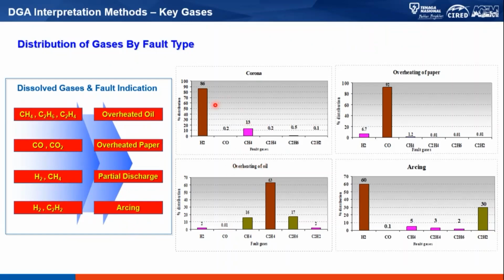Based on the distribution of these gases, you can see here on these bar charts on the right - the composition in terms of distribution, for example for corona or partial discharge, hydrogen is the major gas produced at perhaps lower temperature. When you talk about overheating of paper, more CO or carbon monoxide is produced compared to other gases. And when you talk about overheated oil, a lot may come as an indication from ethylene compared to other heating gases.